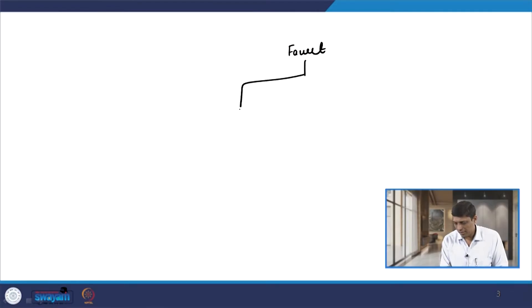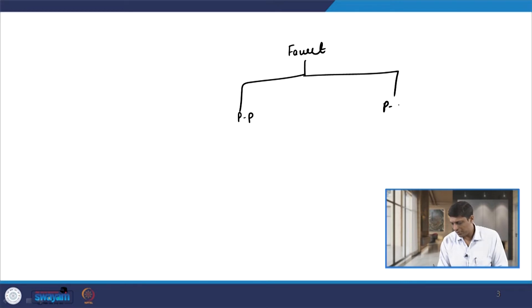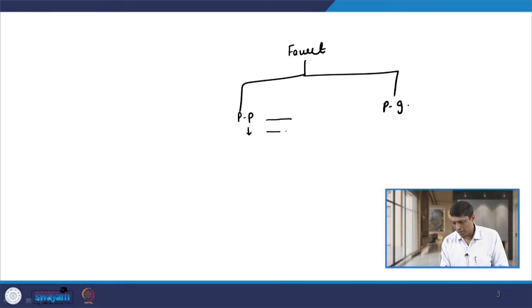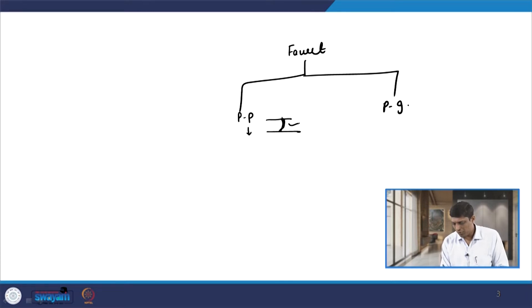This is basically due to the involvement of fault resistance in the earth circuit, which involves the arc resistance. If I consider just the fault current, then we have a phase-to-phase fault and a phase-to-ground fault. Whenever a phase-to-phase fault occurs — when two conductors touch — there is only an arc known as a power arc.